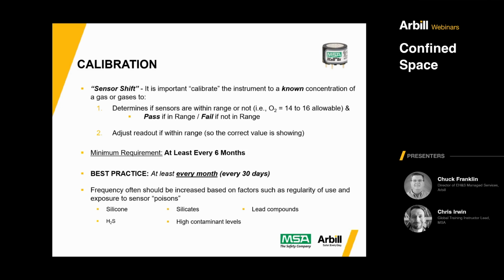When it comes to calibration, we don't want you to go any more than 6 months without doing this, even if you're not using it. And best practice to keep the sensors properly exercised is to do this monthly. I'm a runner, and the example I give is that it would not be a great idea for me to go 12 months and then try to run a marathon the next day without training. Same thing is true here. If I never expose these sensors to gas, and then just expect to take this thing out and use it, it will not work as well. So that's really what calibration does: it helps those sensors know what to look for, and it also tells us that everything's working properly.